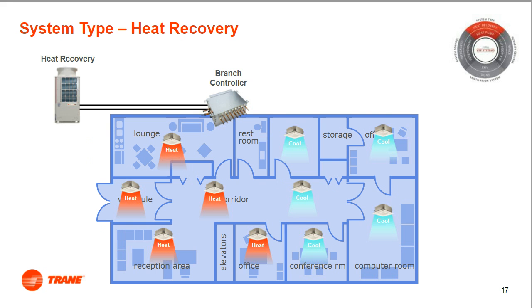Now, a VRF heat recovery system can provide heating in some zones while simultaneously providing cooling in others. All this done on a common refrigerant system. The VRF system uses heat recovery as a technique for providing this capability, thus the name. Heat recovery systems require a unique outdoor unit.